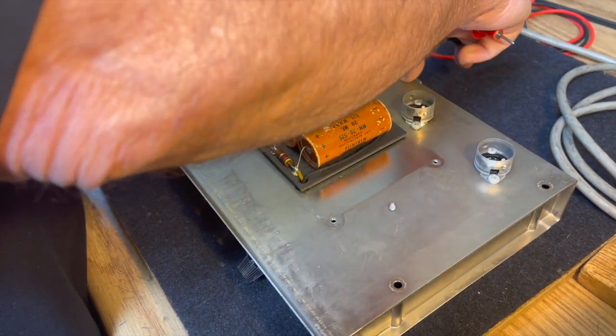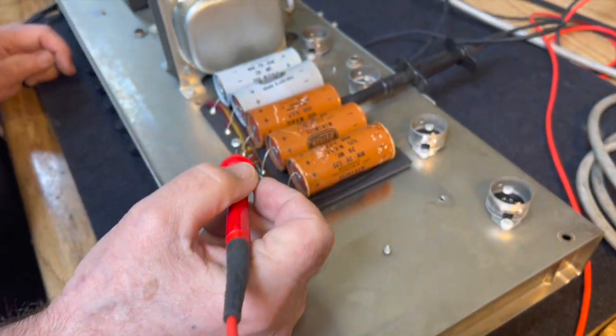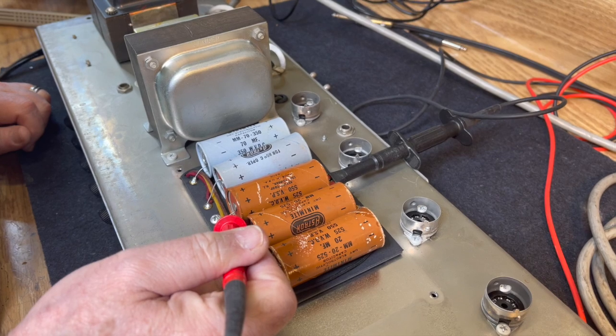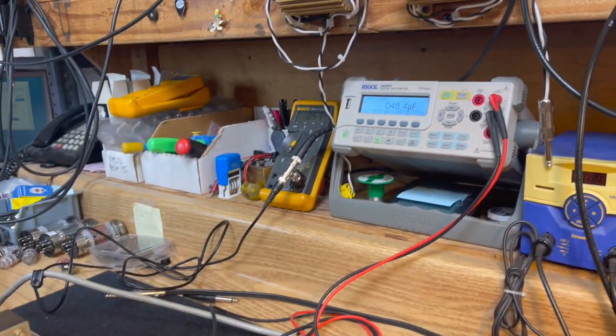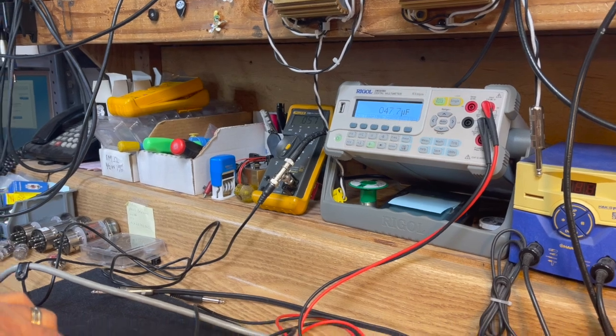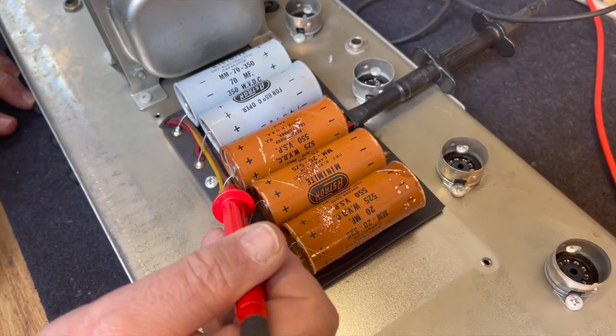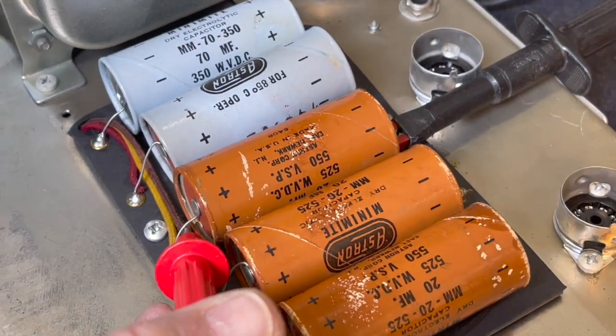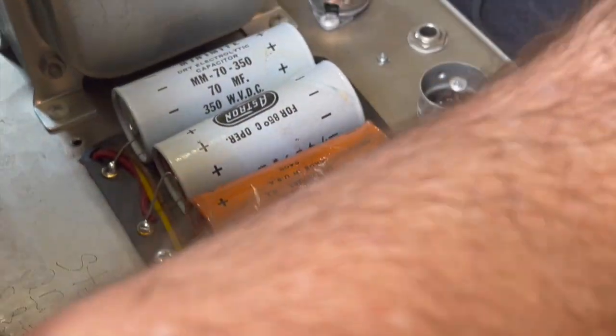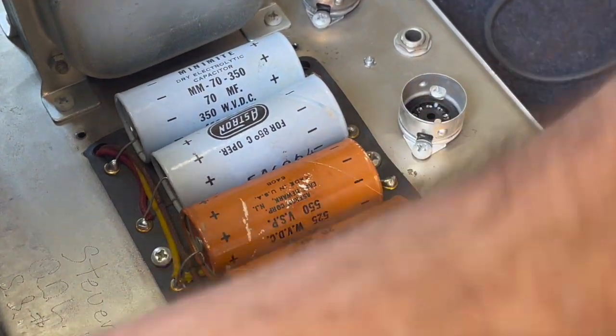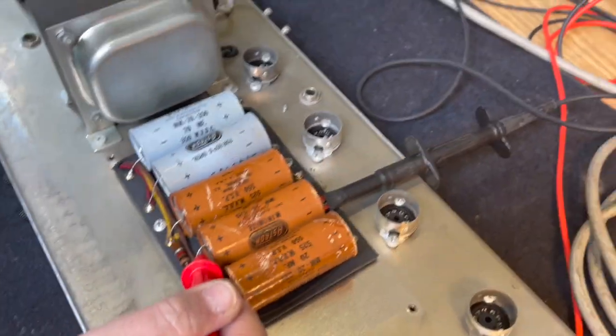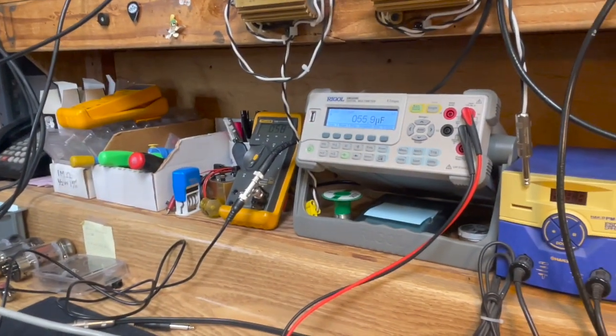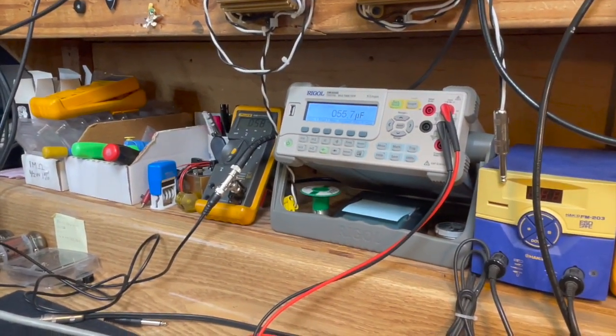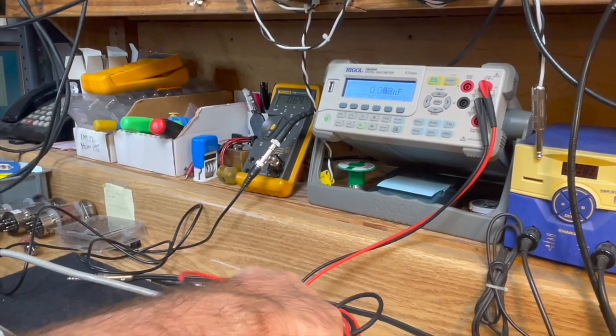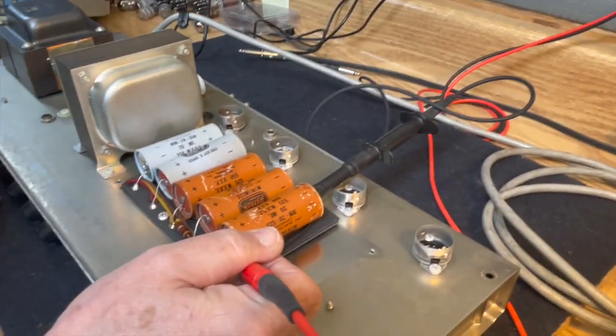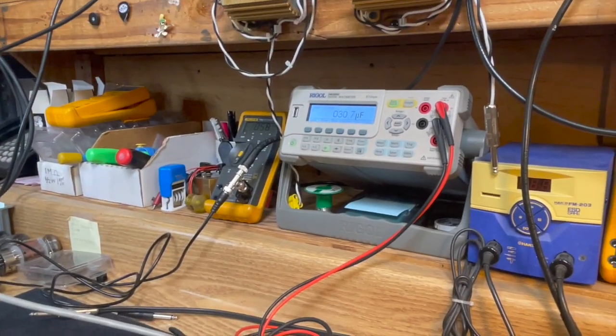Depending on how good the capacitor is, the readings may not vary that much. We'll find out. The next one is a 20 mics at 525 volts, and it's reading 47. These are all grounded to the same point, but I'm putting the meters directly on the negative contact of each one for the lowest path of resistance. This one's reading 55. And this one's reading 50.